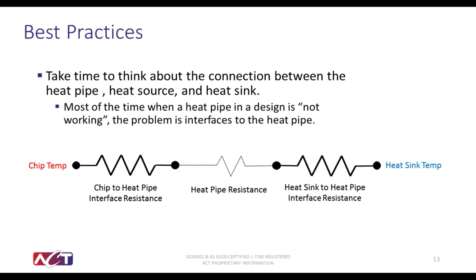If the resistance on one side or the other of the heat pipe is exceedingly large due to improper integration and or an air gap or something of that nature, it may look like that heat pipe isn't working. So our best practice is to take some time and think about the way that you're going to integrate that heat pipe into your condenser and into your evaporator.